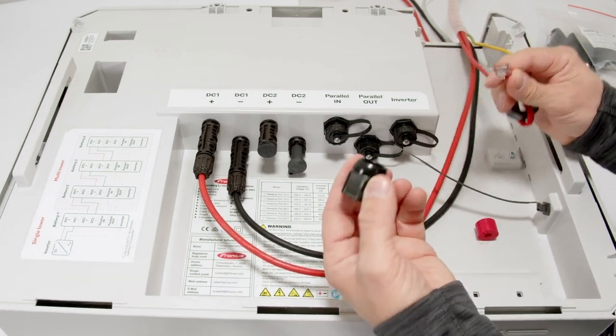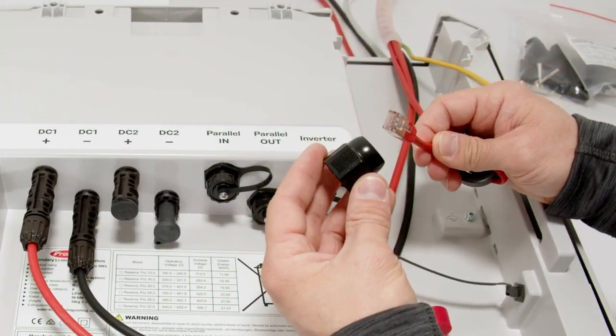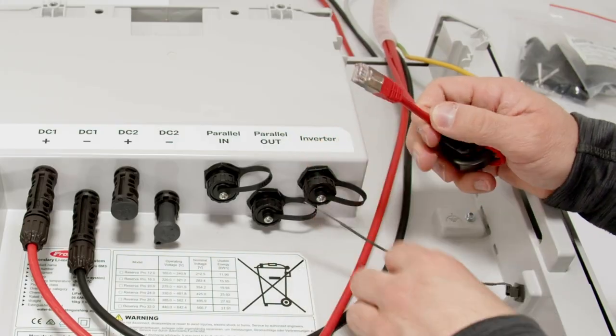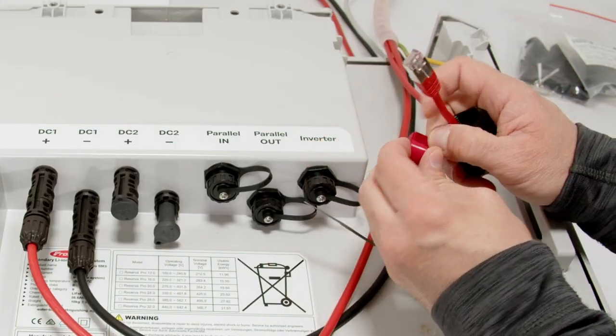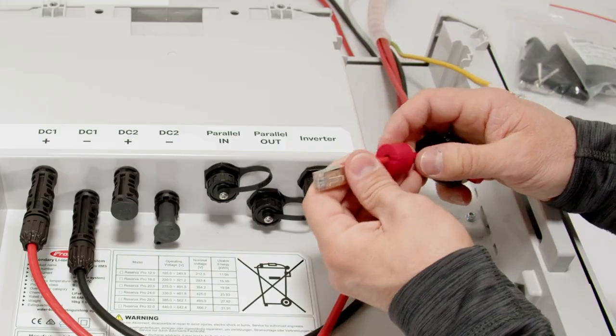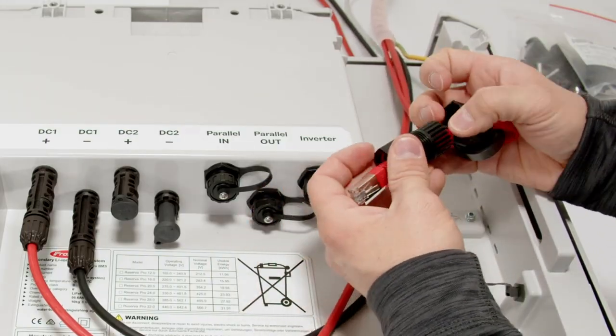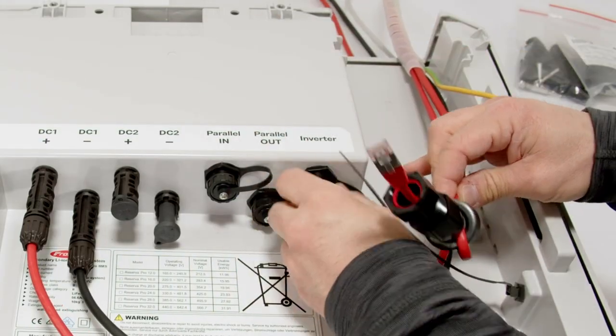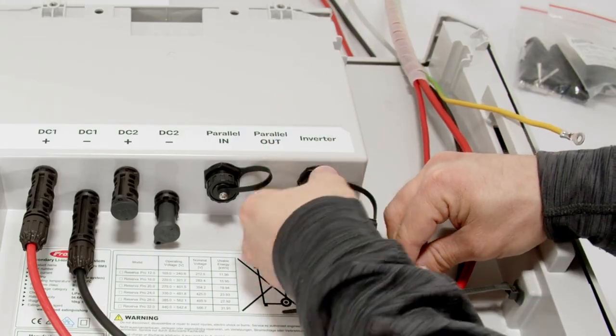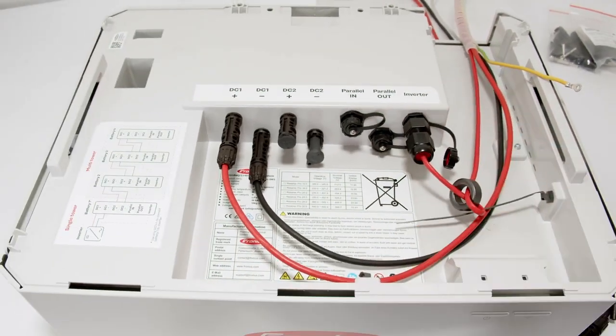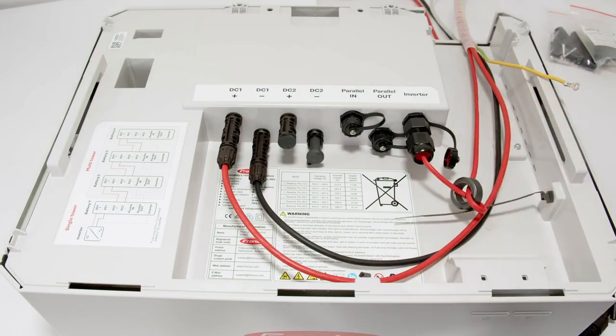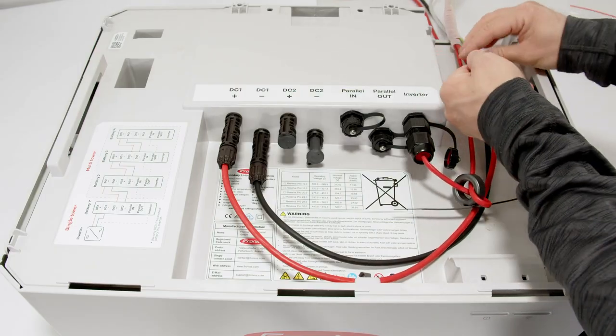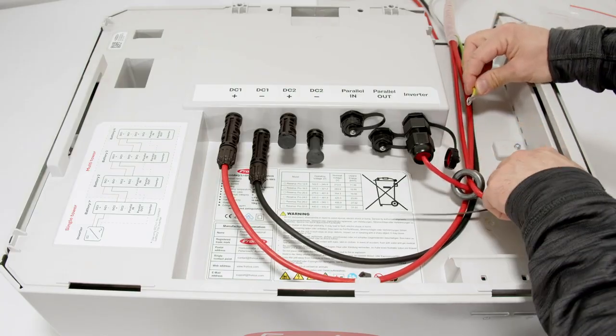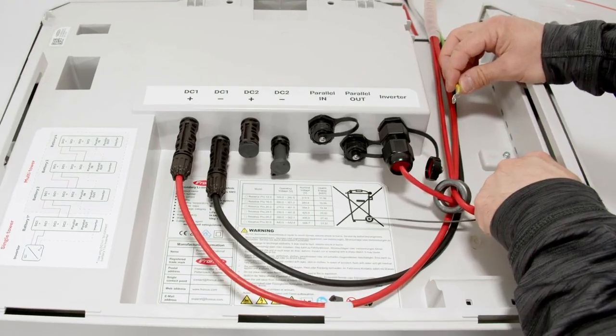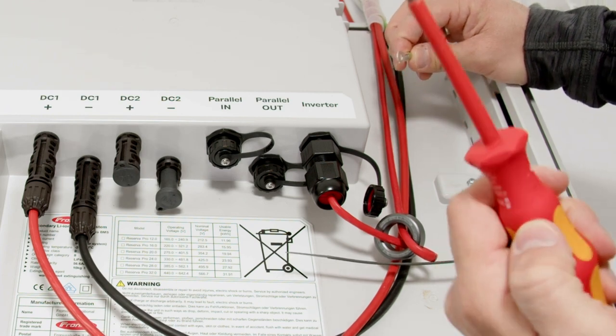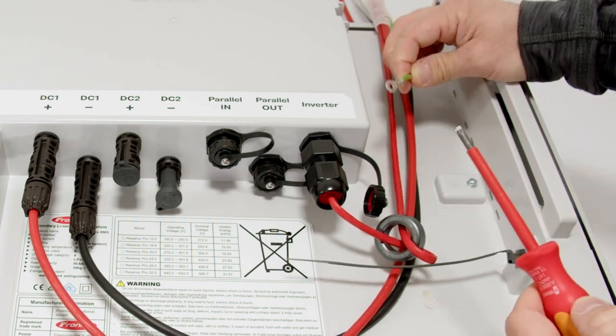For the IP protection cap, you first plug in your protection cap on one hand side, and then you use your slotted shield that you can place over the cable. When we are finished with the inverter cabling, we can then use our protective earth and make the functional grounding of the system. You can do this with this little screw. To screw this down, please take a Torx 20 screwdriver.